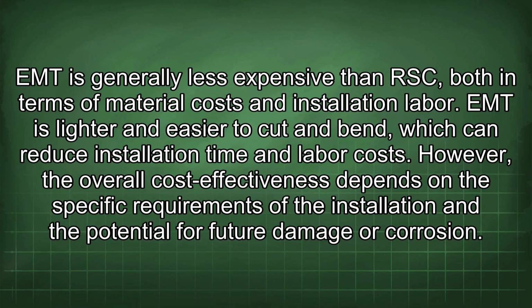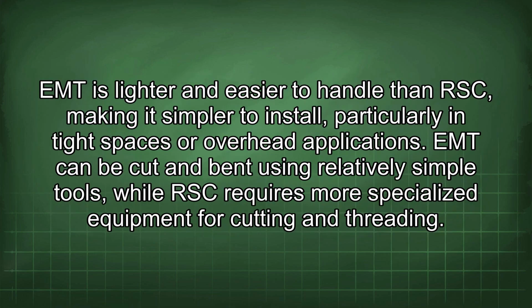EMT is lighter and easier to cut and bend, which can reduce installation time and labor costs. However, the overall cost effectiveness depends on the specific requirements of the installation and the potential for future damage or corrosion.